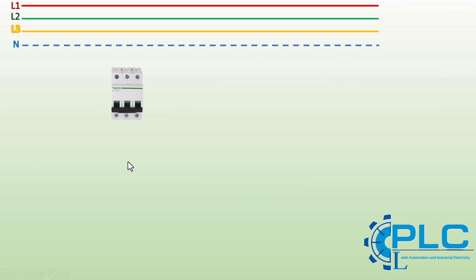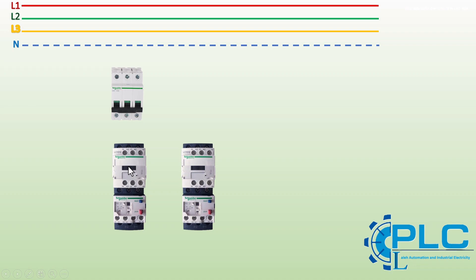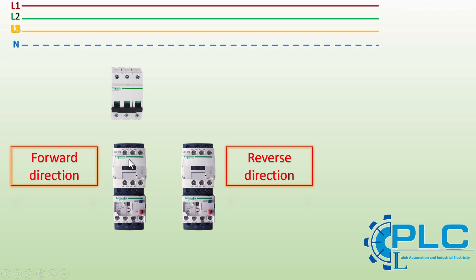In our project, we will use two contactors to control this phase swapping automatically. One contactor will connect the motor to run in the forward direction, and the second contactor will reverse the motor's direction. However, both contactors should never be active at the same time, as this could cause a short circuit.